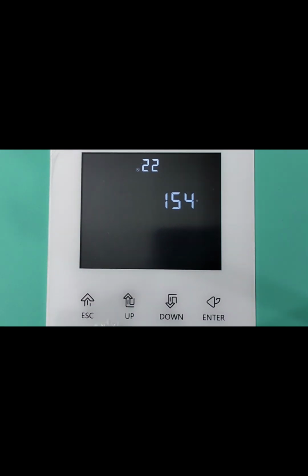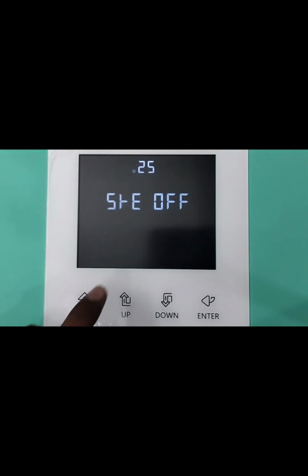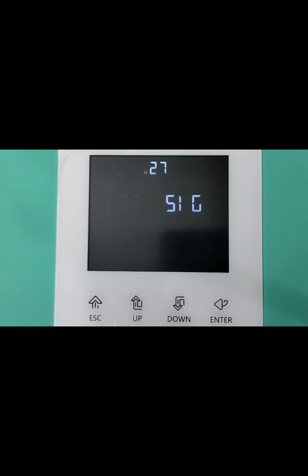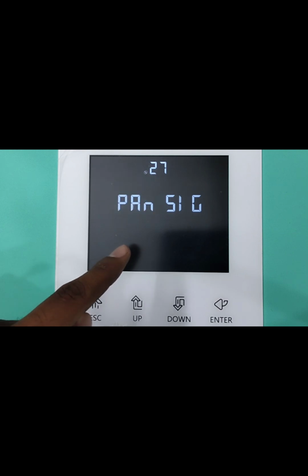Option 22. When the main voltage, means grid voltage, will get low, it will alarm at this point. Main high voltage protection, low discharging time, inverter soft start setting, reset factory setting. Option 27. This is parallel mode setting. On this setting you can change if the inverter is running at grid only.